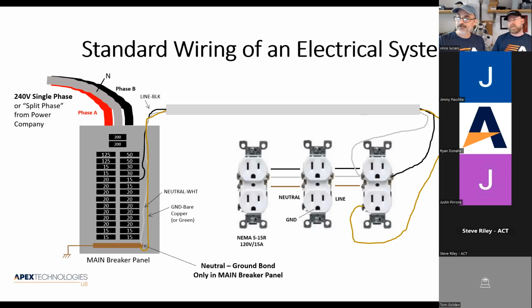Stop on that point really quick, because what I usually hear, from the audiophile type or the homeowner, is: hey, we have a dedicated 20. How do you have good power? Oh, I have good power. I have a dedicated 20 amp circuit. Yeah, that really goes to the point you just made about lowering impedance. It does not necessarily mean it's clean. Oh, correct, because there could be things polluting it upstream. It's definitely on our list of best practices to have dedicated outlets. It helps, but it's not a guarantee that the outlet is not a problem.